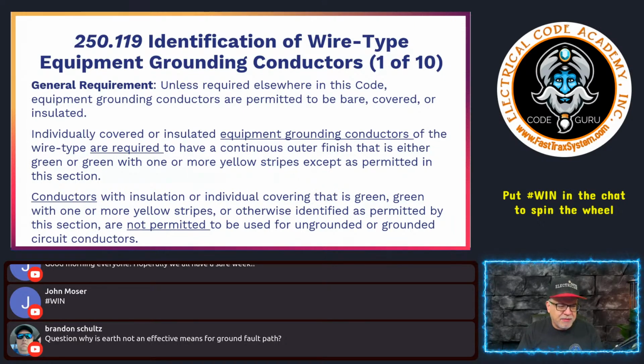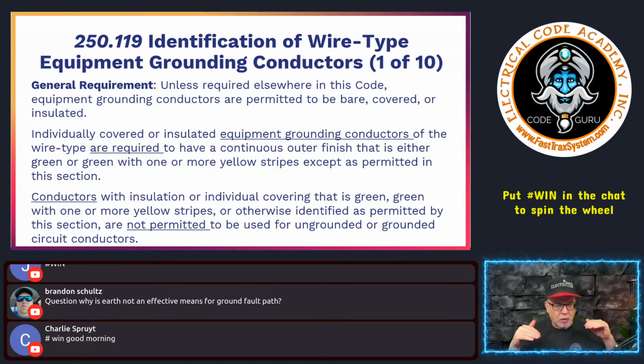The earth is not an effective ground fault current path. Absolutely, it's not. But you still have to connect to it because it stabilizes voltage. Right? You have to have that reference point, that zero point. So you have that connection through the system. That's why we connect to earth on a grounded system. That's that function. So it is to clear an overcurrent device, to give a low impedance effective ground fault current path back to the source.